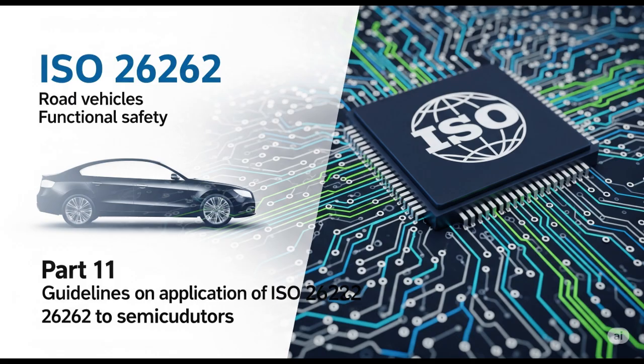And for self-testing, analog built-in self-test, or ABIST, involves designing circuitry that can exercise diagnostic paths by injecting specific currents or voltages. This ensures that the monitoring circuits themselves can correctly switch between detecting faulted and non-faulted states, verifying their proper operation without needing complex external test equipment.